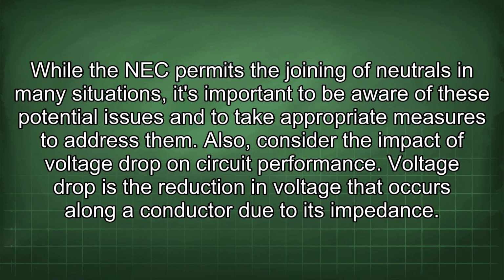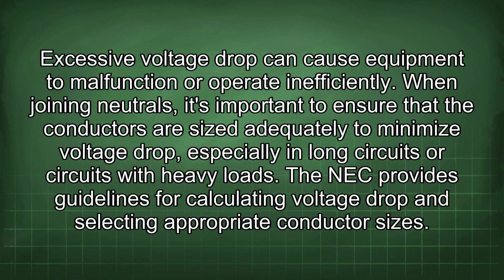Also, consider the impact of voltage drop on circuit performance. Voltage drop is the reduction in voltage that occurs along a conductor due to its impedance. Excessive voltage drop can cause equipment to malfunction or operate inefficiently. When joining neutrals, it's important to ensure that the conductors are sized adequately to minimize voltage drop, especially in long circuits or circuits with heavy loads. The NEC provides guidelines for calculating voltage drop and selecting appropriate conductor sizes.